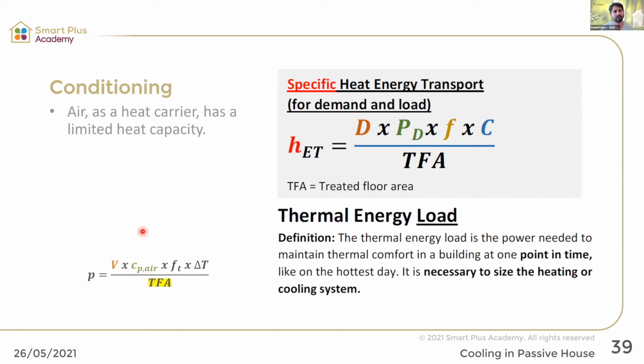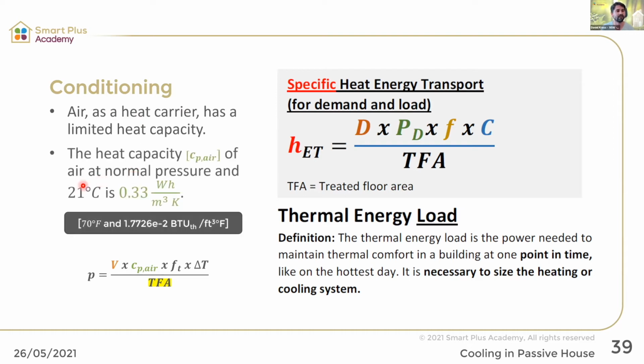Then here I explained already the air has a heat carrier, has a limited capacity, the thermal mass that that air has. At 21 degrees, the heat capacity is 0.33 watt hours per cubic meter Kelvin. This figure is not really temperature dependent. If you go really far back, it changes slightly, but we're always using the 0.33 watt hours per cubic meter Kelvin in our calculations. And that's that part of the formula. And if you wonder what that is, that's the magic formula. That's the magic formula that we are teaching.